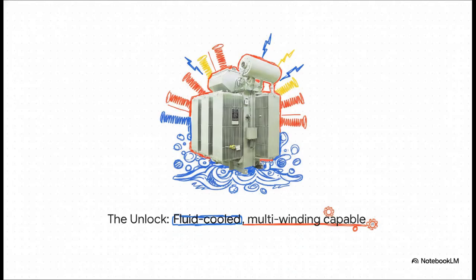Okay, so here is the big unlock. By explicitly choosing to submerge the windings in an insulating fluid instead of casting them in solid resin, you open the door to entirely new electrical configurations. Things that standard dry types simply can't pull off. Yes, you get a highly robust fluid-cooled unit, which is great, but the absolute most critical capability this physical change unlocks is the ability to easily build multi-winding transformers.